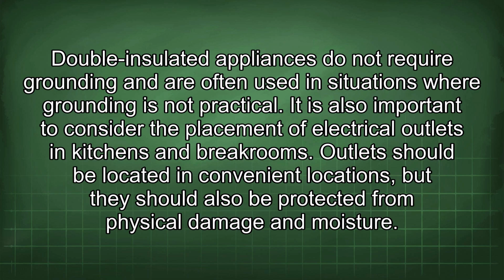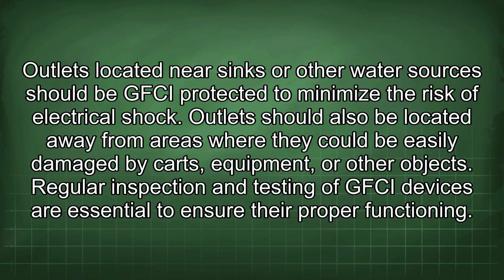It is also important to consider the placement of electrical outlets in kitchens and breakrooms. Outlets should be located in convenient locations, but they should also be protected from physical damage and moisture. Outlets located near sinks or other water sources should be GFCI protected to minimize the risk of electrical shock. Outlets should also be located away from areas where they could be easily damaged by carts, equipment, or other objects.